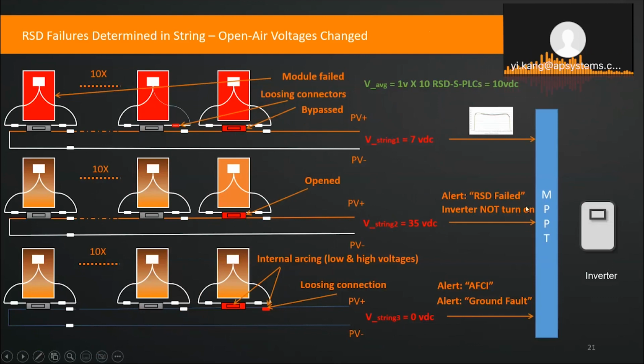For SMA inverters, actually, they internally set up a program. If they find out they suddenly have a higher voltage, they will alert you. They call it RSD fail. So for SMA customers, you need to pay attention to this. If this alert comes out, it means somewhere was shorted with high voltage.